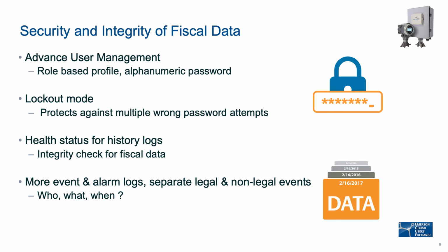Even after that, if somebody is trying to crack the password, then device can go itself in a safe lock mode after seeing multiple wrong password attempts. Regarding the data which we log inside the unit for history, we also log a quality bit along with the value of individual records, and that helps to find out any kind of integrity issue. The questionable integrity can be like the data was in manual override mode or alarm mode or fault mode, etc.